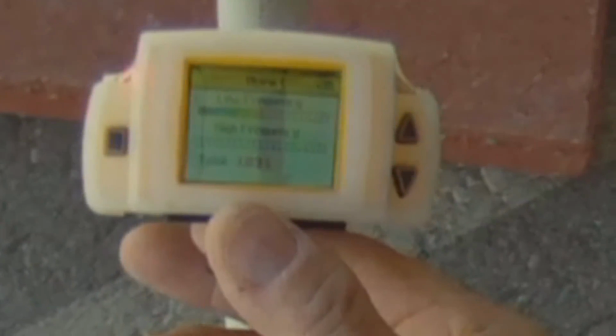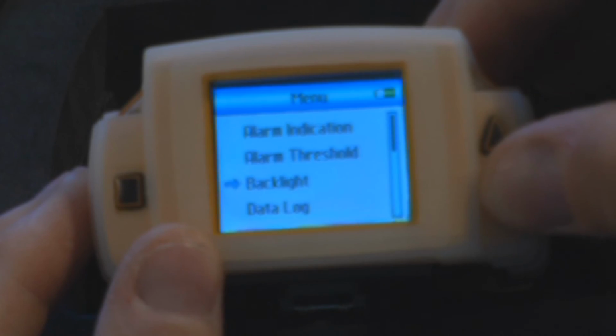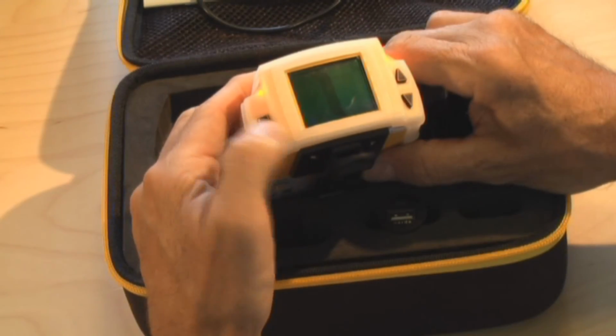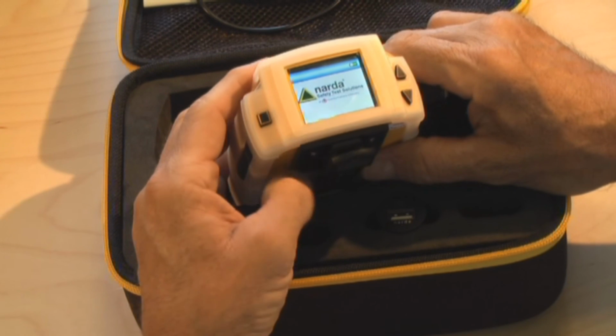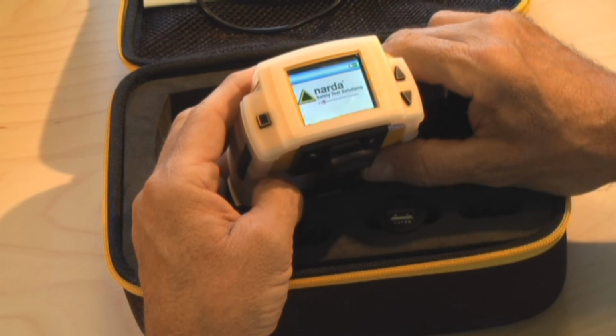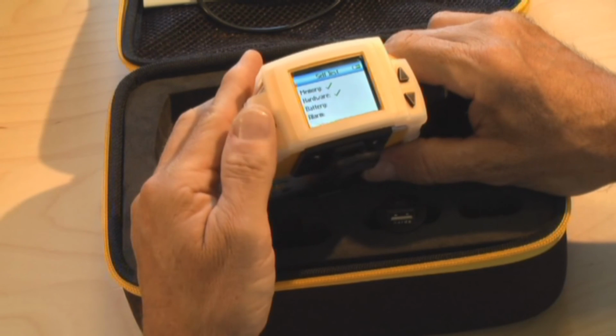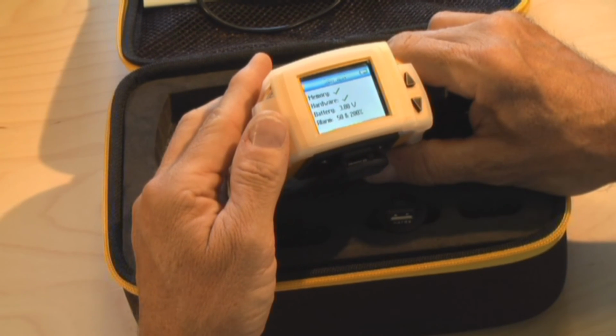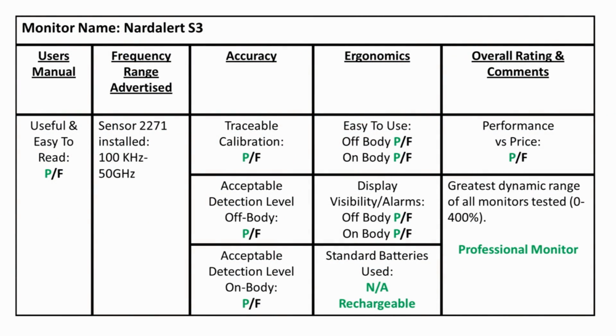This unit easily passed all of our accuracy tests. I found that it has numerous features and yet is extremely easy to use, including menu navigation. It also had the greatest dynamic range of all the monitors tested, with 400% of the occupational limit being detected and displayed. With the high visibility screen, LEDs, audible alarm, and rechargeable battery, it scores very high in ergonomics too. This was the most expensive monitor, but in this case, you get what you pay for.